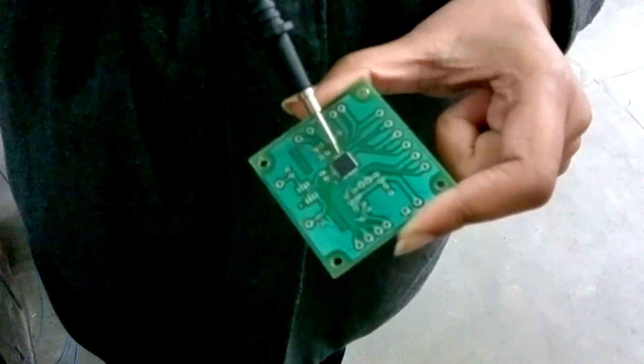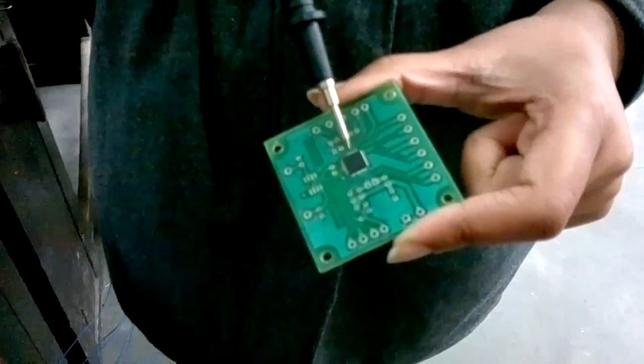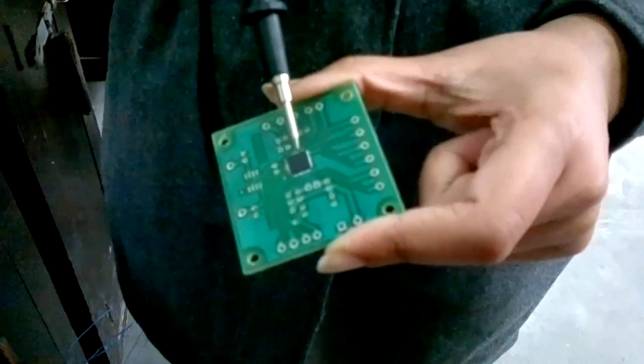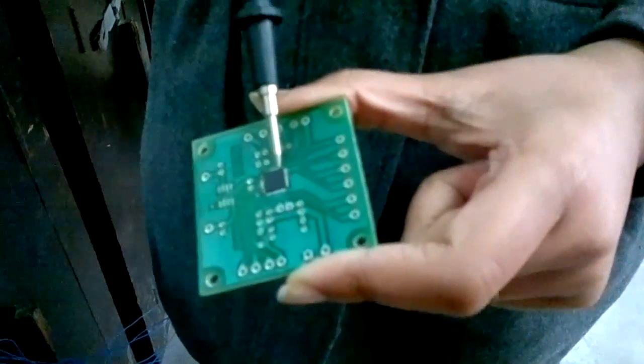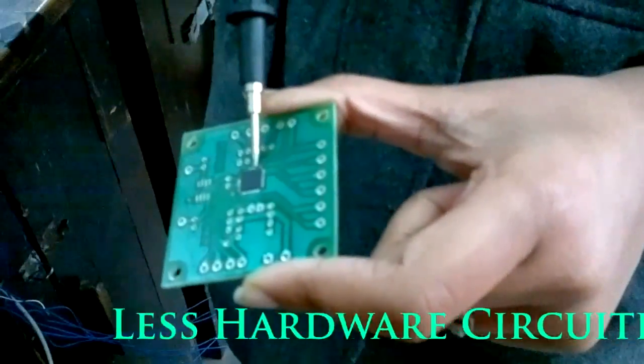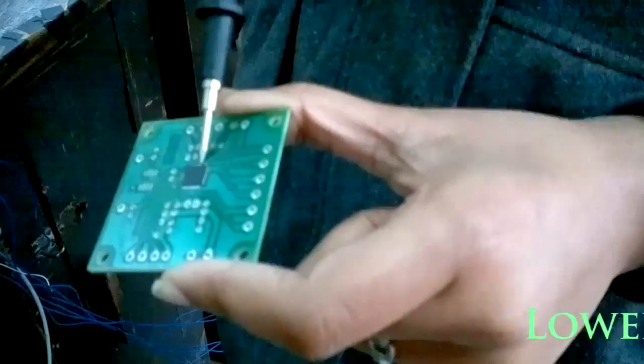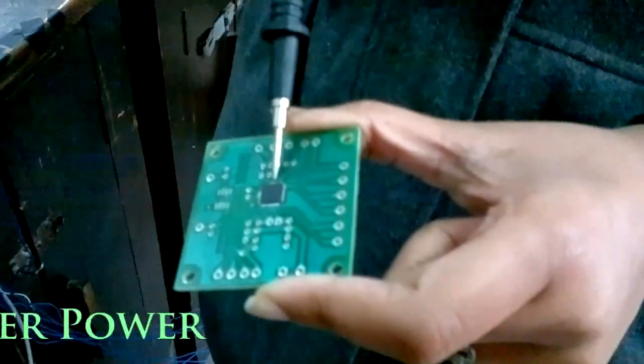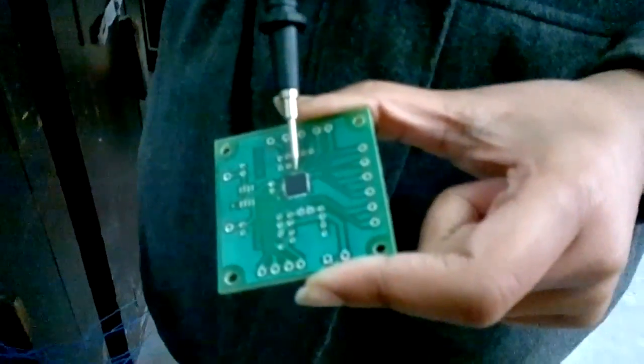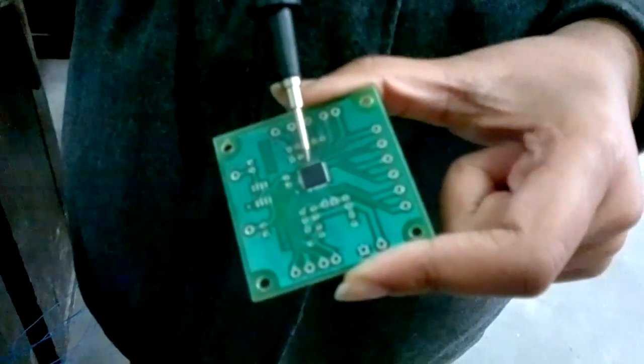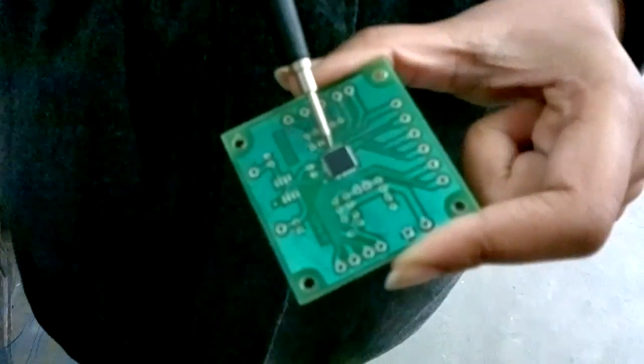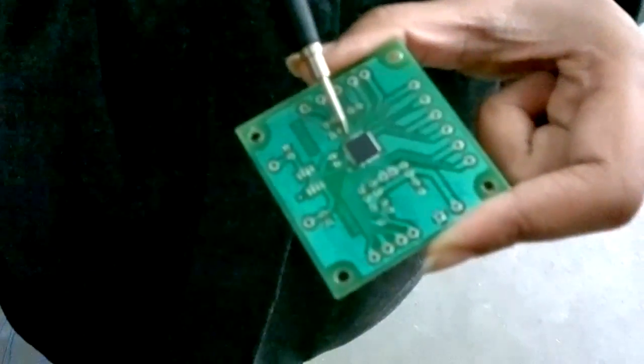It has been used as it provides a sequential sampling approach as compared to simultaneous sampling. This sequential sampling requires less hardware circuitry, which implies both lower cost and lower power. The DC blocking high-pass filter is also eliminated because the inherent noise of this ADC is significantly lower than the previous solution. A 32.768 kHz crystal oscillator is being used here, which provides the clock for sampling.